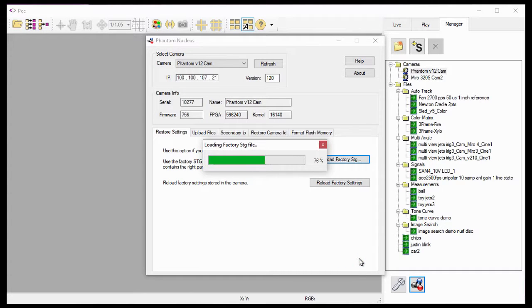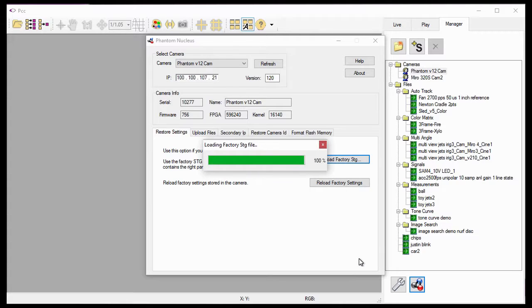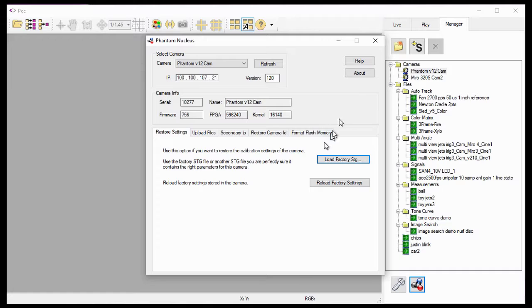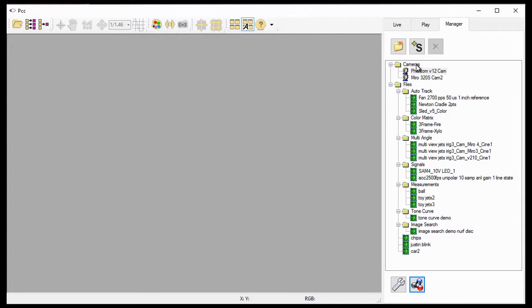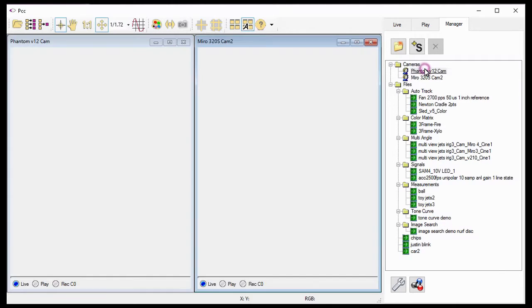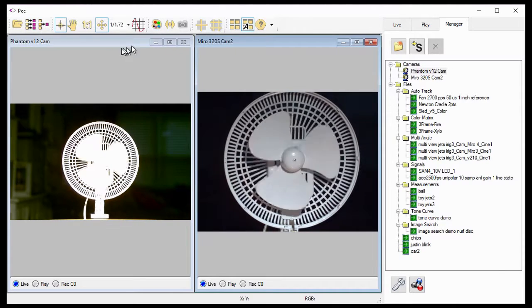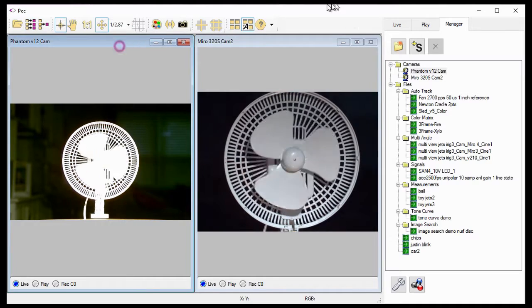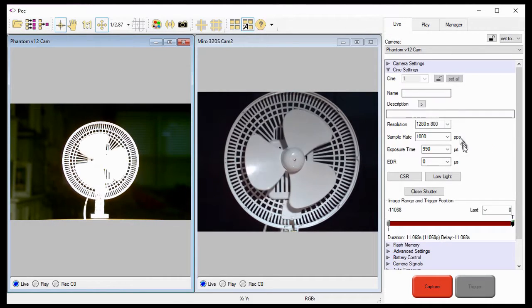The software displays a Load Factory .stg file progress window. Once the process completes, I can close the Load Factory .stg file window. The camera has now been restored to the factory camera image calibration and camera-specific settings data and is ready for use.